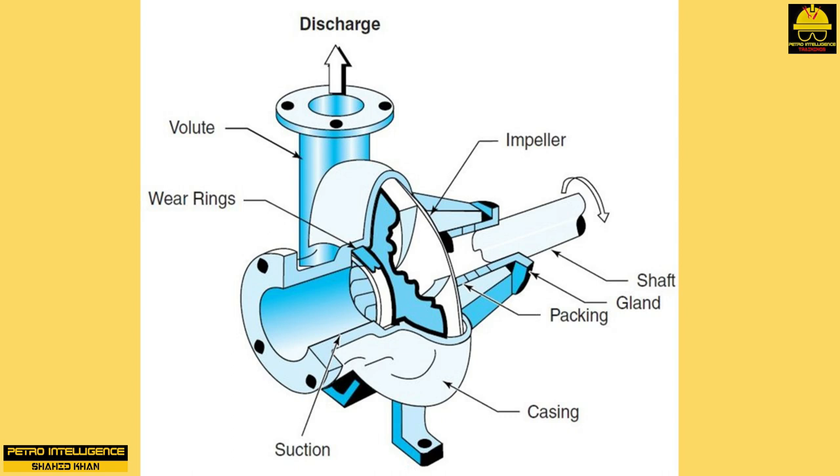Radial bearings along the shaft minimize side-to-side movement. Thrust bearings eliminate axial movement along the shaft. Between the bearings and seals, a loose-fitting flinger ring mounted on the shaft conveys lubricant onto the bearings. The ring rotates on the shaft, but at a lower speed. Mechanical seals installed where the rotating shaft enters the casing minimize or stop leakage from the internal components of the pump. Mechanical seals are composed of a stationary face and rotating face that fit closely. Seal faces may require lubrication or cooling.